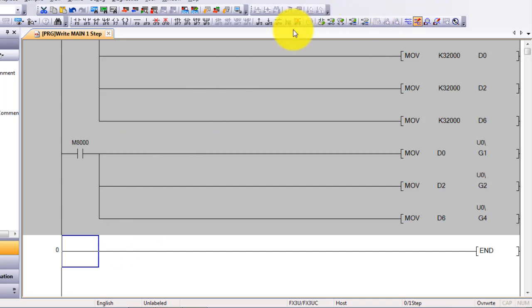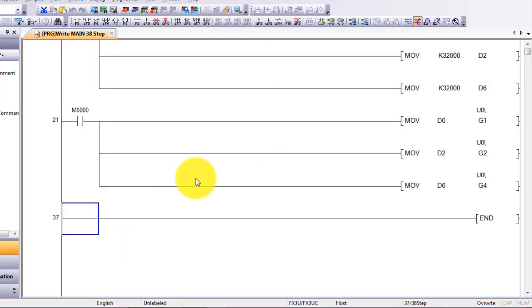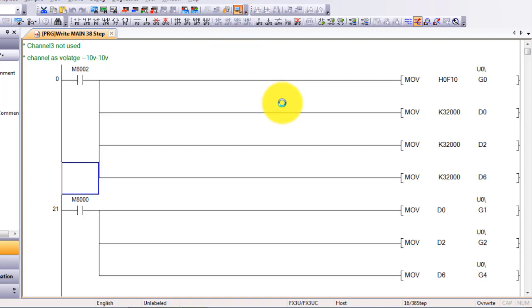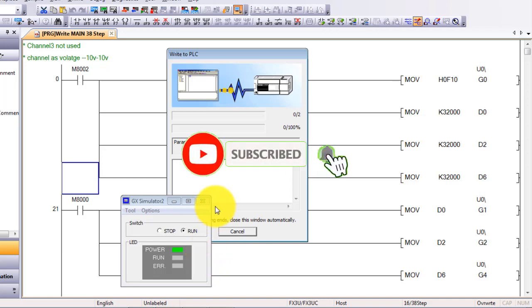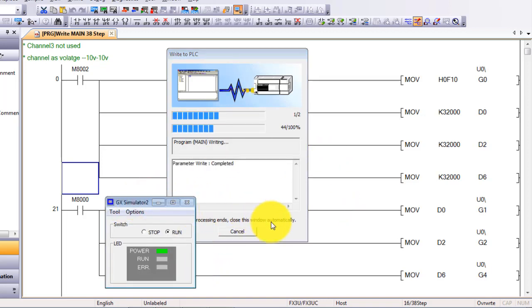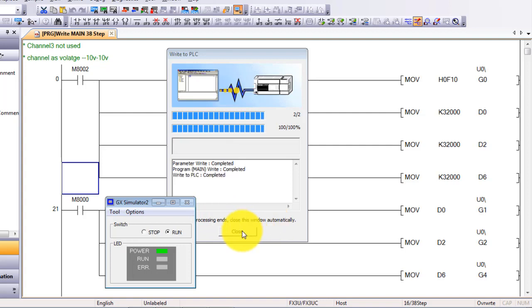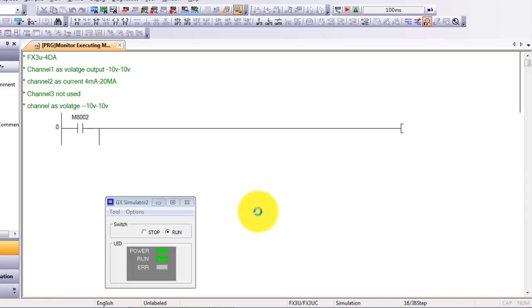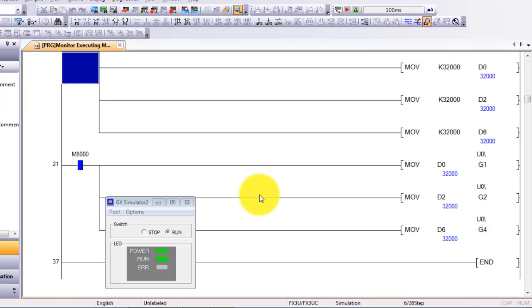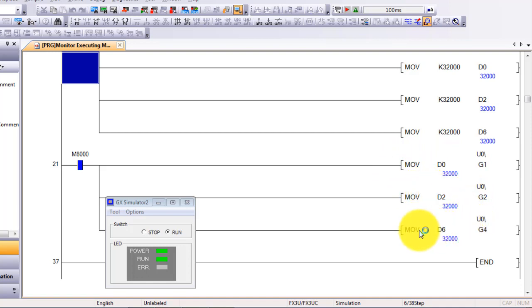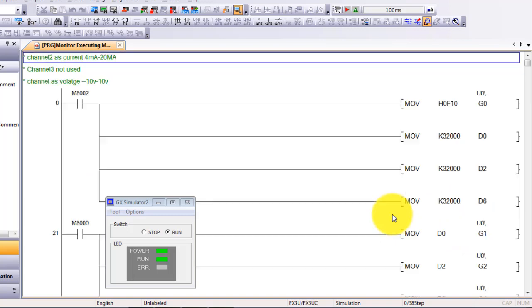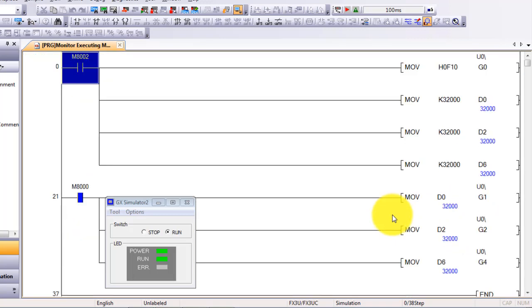These are the complete programming steps for the analog module. I will compile the program — there are no errors. Going to simulation, with the maximum values set by this programming: channel 1 will give plus 10V, channel 2 will give maximum 20mA, and channel 4 will show plus 10V. If you have any questions regarding this lecture, you can write in the comments or contact via WhatsApp number. Bye.